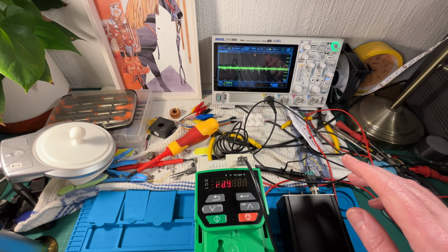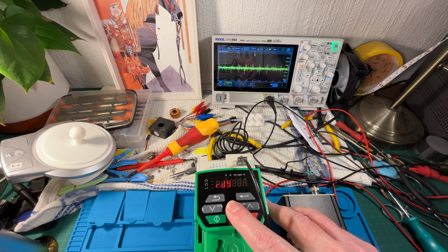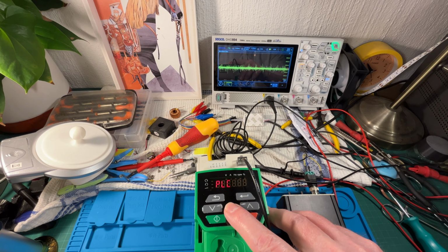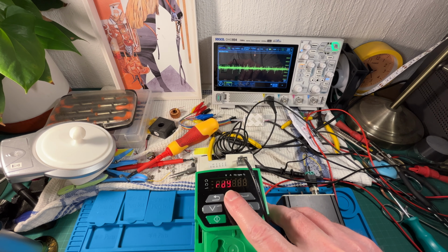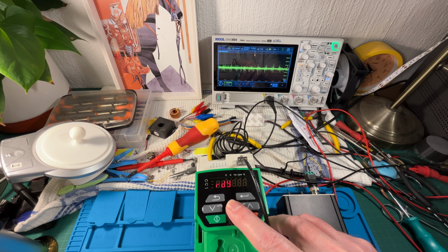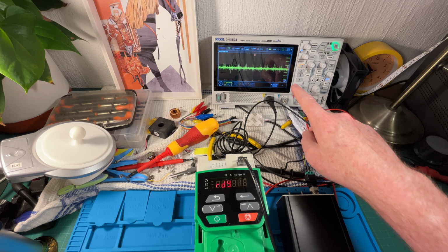What I'm going to do is I've set this up so that it can run up to 100 Hertz. In other words, we're going to run super synchronous. So we're going to run this motor into what's called the constant current region, constant power region, which is when you go above base frequency, which is 50 Hertz. Because beyond that your voltage stays constant and your current decreases. So you're going to see the current waveform change there on the scope.